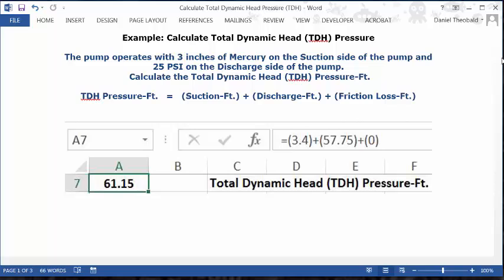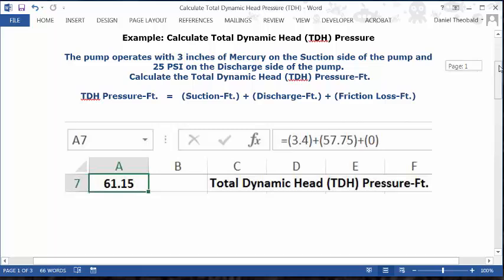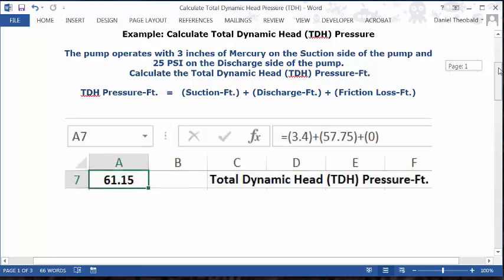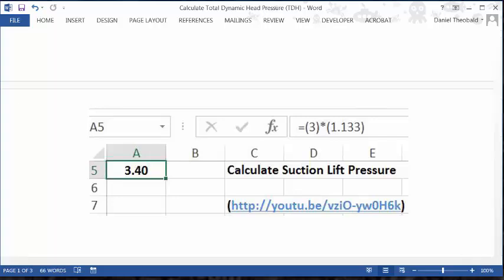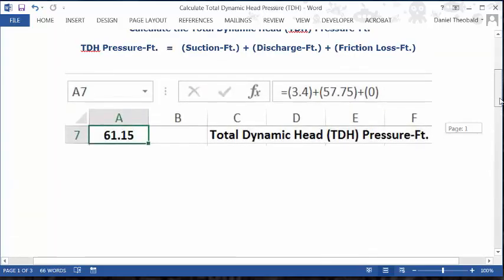Let's see how we calculated the suction pressure, which we inserted as 3.4, using the data in the problem. The suction lift pressure is calculated by taking inches of mercury times the conversion factor to feet of head pressure, 1.133. So 3 times 1.133 equals 3.40. This is the formula, the description, the URL, and the answer — that's where we got our 3.4 for the formula.